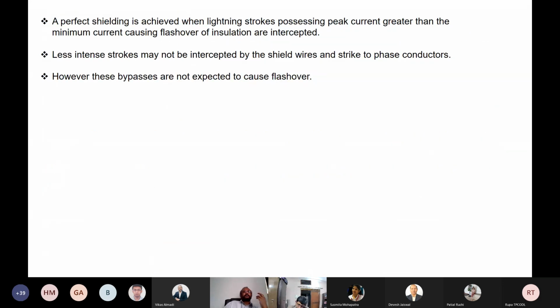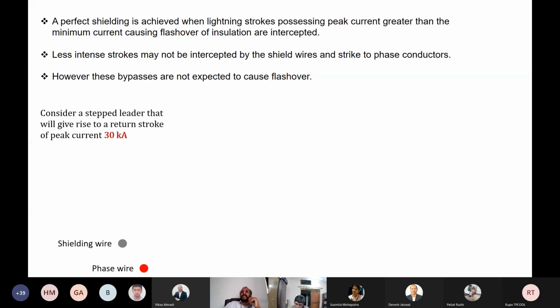Okay, now a perfect shielding is achieved when lightning strokes possessing peak current greater than the minimum current causing flashover of insulation are intercepted. Now I'm going to another important point, which many people usually do not understand properly, as per my experience in the field. Before going into the explanation, let me put it this way. If I make a statement like this, the chances of a 30 kiloampere amplitude lightning current getting attached to the shielding wire is much higher than a 3 kiloampere amplitude lightning getting connected to the same shielding wire.